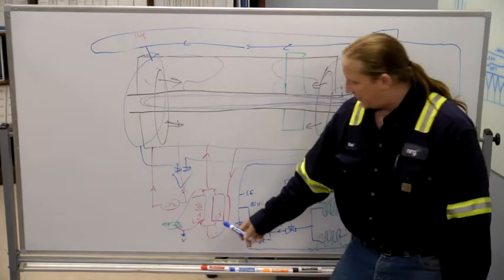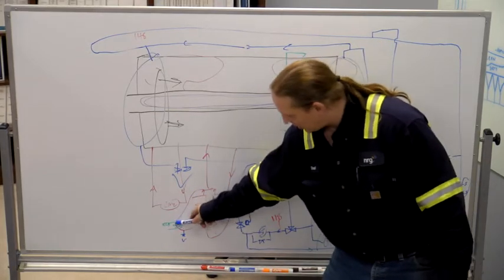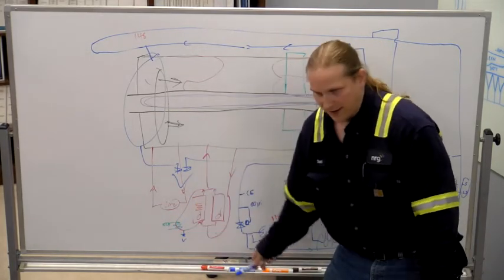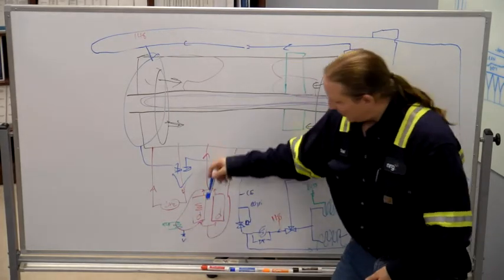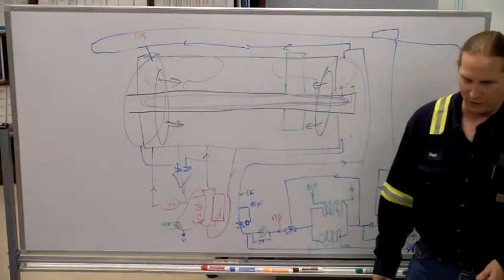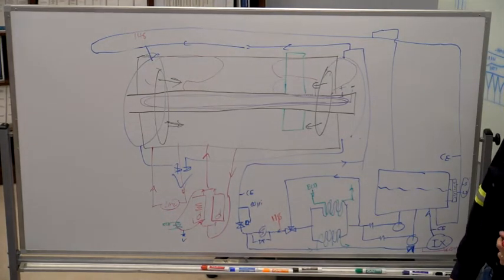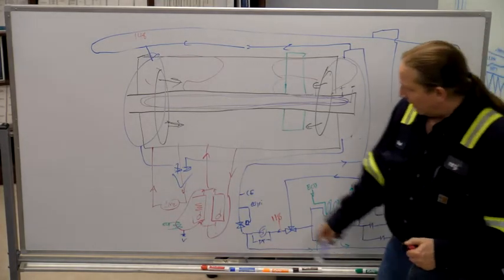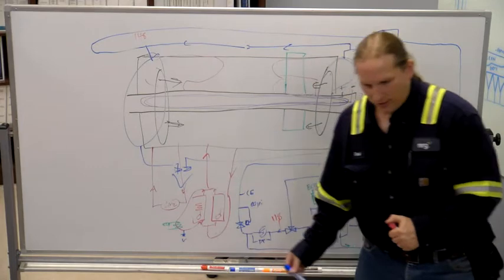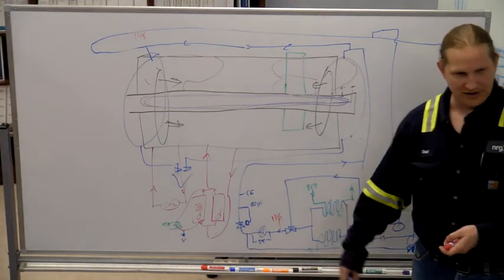And then it's got like a little collecting pot and a drain. So you heat the desiccant to make it give up the moisture, and then you cool the hydrogen back off, and the moisture falls back out. And then there's a little drain that detects when there's water there, and it opens up, and it dumps the water into a funnel on the ground. I have the impression that it's not a lot of water, that it's like an hour cycle, and then we're talking less than a cup of water gets dumped out of it.